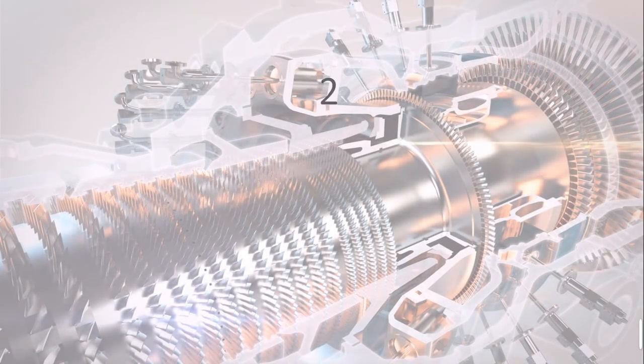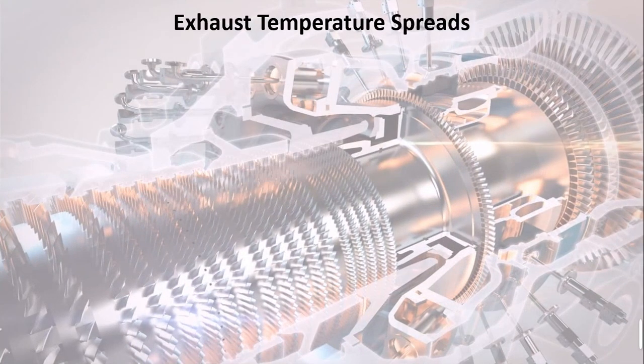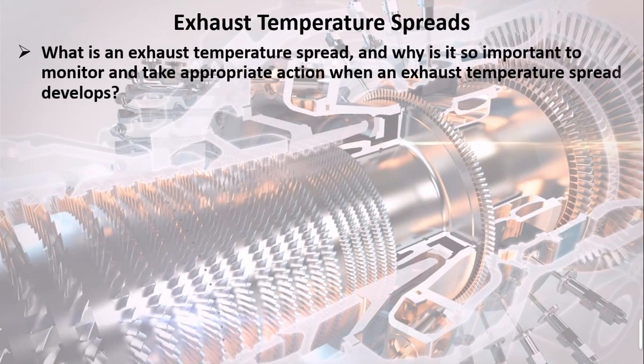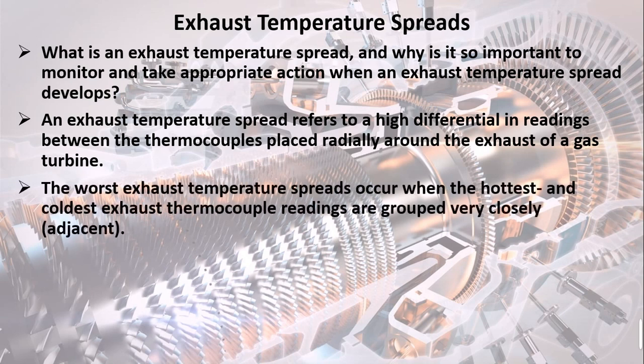Reason 2: Exhaust temperature spreads. What is an exhaust temperature spread, and why is it so important to monitor and take appropriate action when an exhaust temperature spread develops? An exhaust temperature spread refers to a high differential in readings between the thermocouples placed radially around the exhaust of a gas turbine.